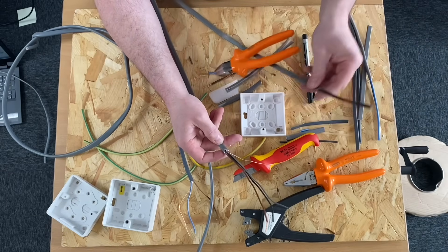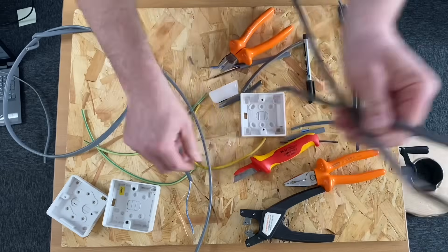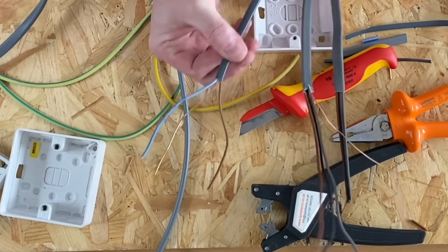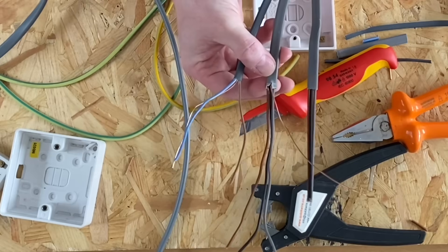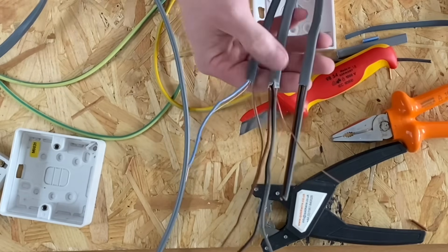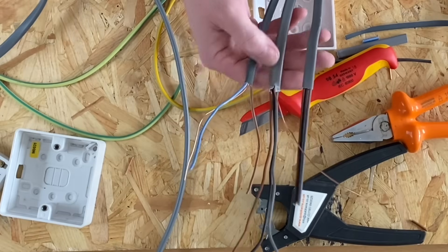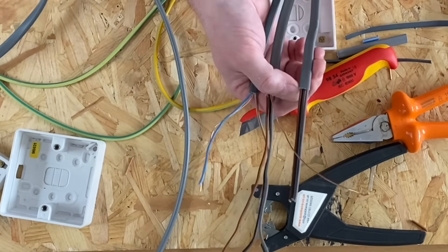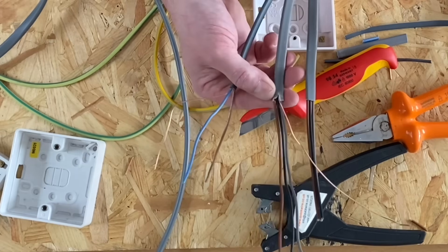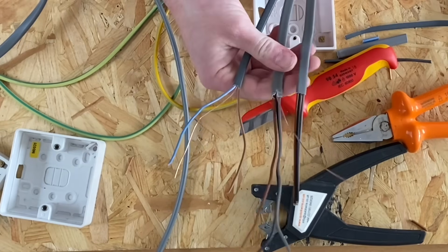Okay, we're looking for ends, I know we did this one and this one here, three different methods. You can see that's used the combination wire strippers, that's used the knife and that's used the technique that wouldn't look pretty in a box. I know we're never going to see it, okay, but that doesn't look very good at all and I like my ends to be nice and square. No damage to the inner insulation, okay, and that PVC there looks a little bit untidy.